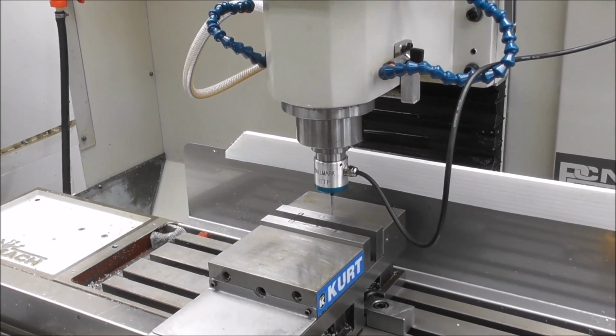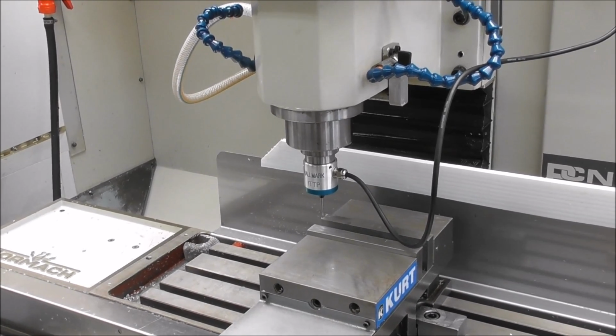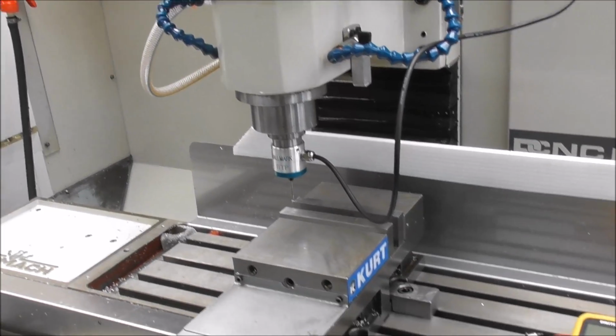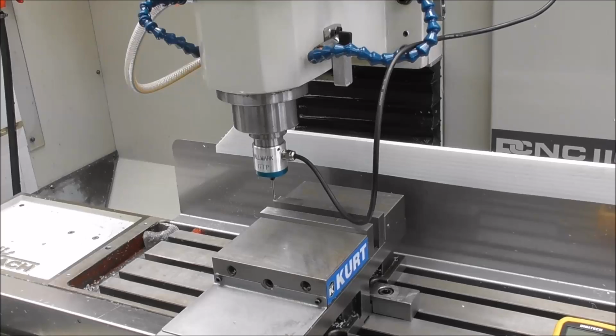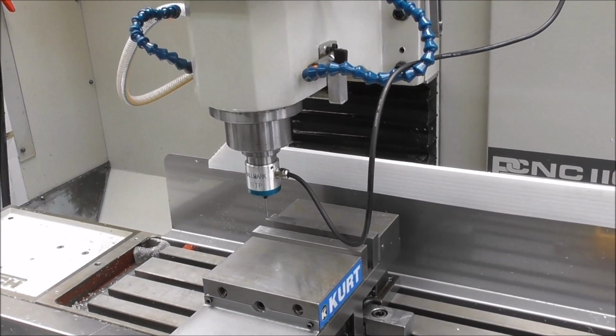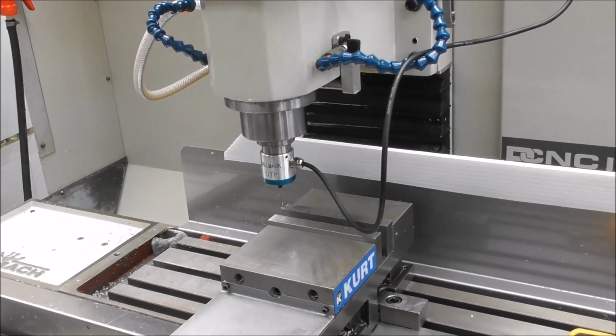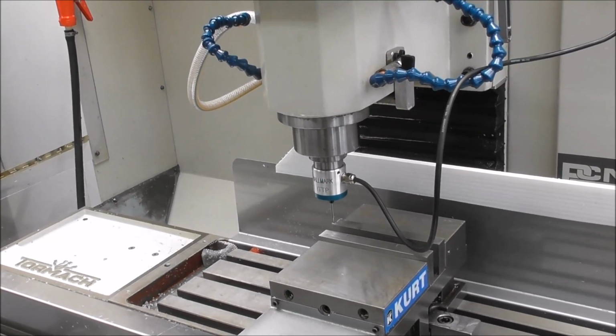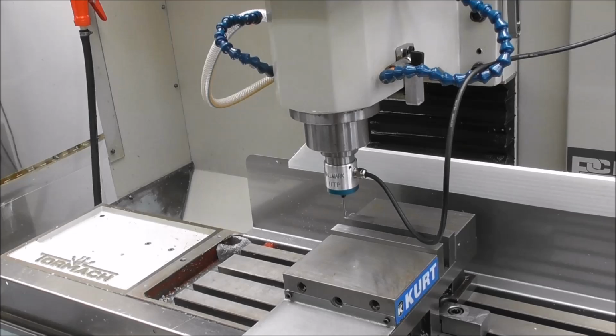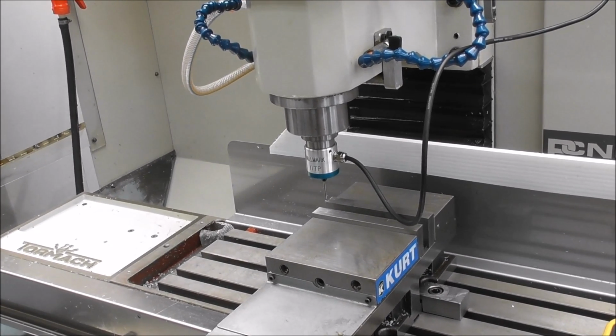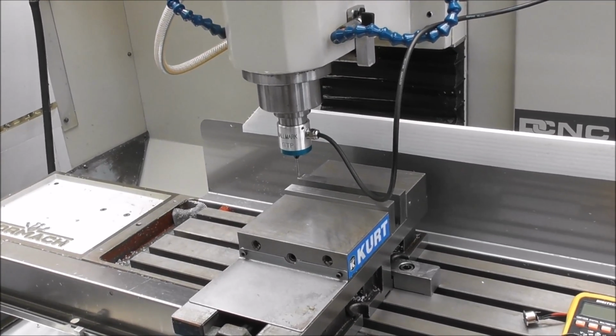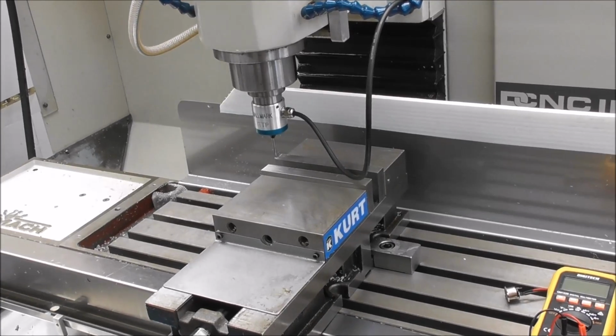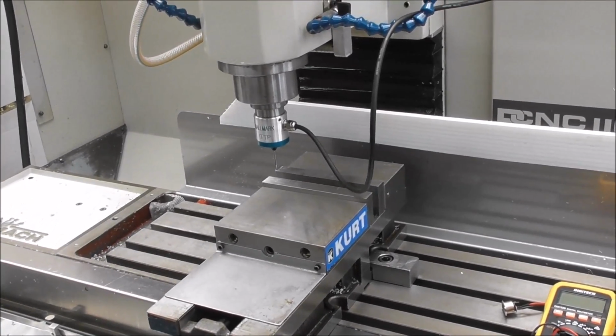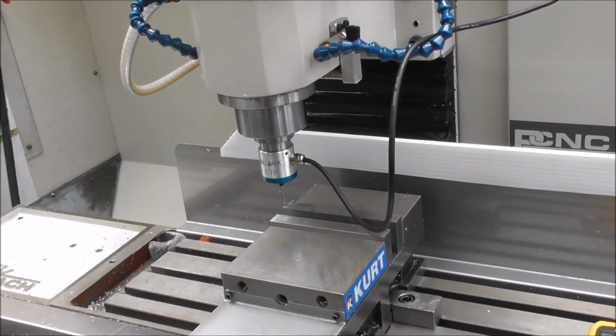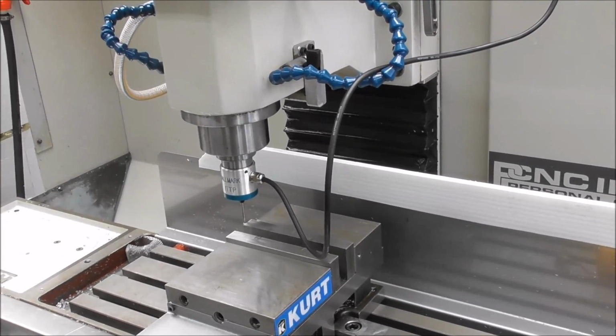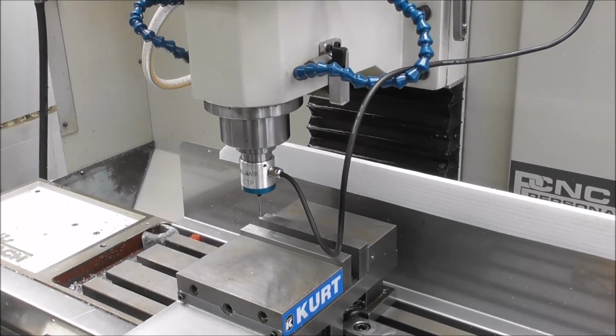And the advantage of this is that it does about 20 switches and finds an XY coordinate position relative to the part, and then you can put in another work offset, G55, G56, and so on, and repeat the procedure, and then go to XY0 and then scroll between the different G work offset positions and check that it's accurate. So that tests for reliability and accuracy. But that's a pretty kind of clunky way of checking a probe. If you really want to check it efficiently, I found it's much better to try and find ways of measuring precursors to issues. I'll just set up now and show you that.